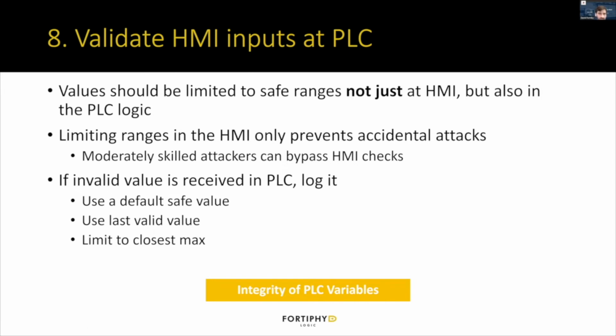The next practice is validating HMI inputs at the PLC itself. Values should be limited to safe ranges, not just at the HMI, but also in the PLC logic. It's good to limit the values to safe ranges at the HMI so you don't accidentally try to set something to a bad value. But most control system protocols are not authenticated, so an attacker can just send a command over the network, bypass the HMI, and write the Modbus register or write an ENIP variable to cause some problems. Having actual safety checks within the PLC itself helps prevent those issues.